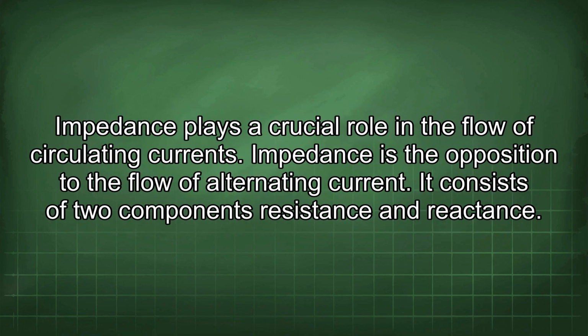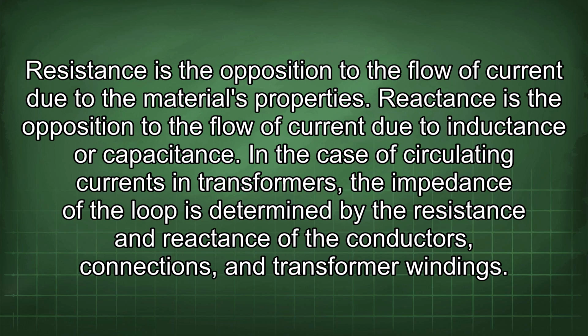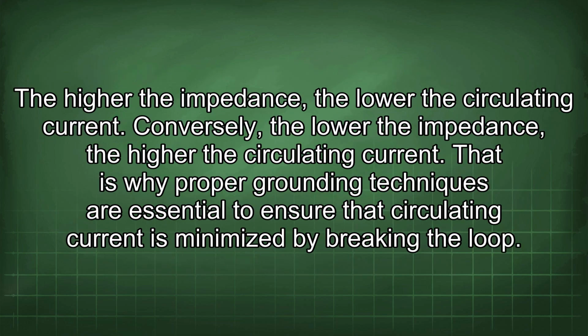Impedance plays a crucial role in the flow of circulating currents. Impedance is the opposition to the flow of alternating current. It consists of two components, resistance and reactance. Resistance is the opposition to the flow of current due to the material's properties. Reactance is the opposition to the flow of current due to inductance or capacitance. In the case of circulating currents in transformers, the impedance of the loop is determined by the resistance and reactance of the conductors, connections, and transformer windings. The higher the impedance, the lower the circulating current. Conversely, the lower the impedance, the higher the circulating current. That is why proper grounding techniques are essential to ensure that circulating current is minimized by breaking the loop.